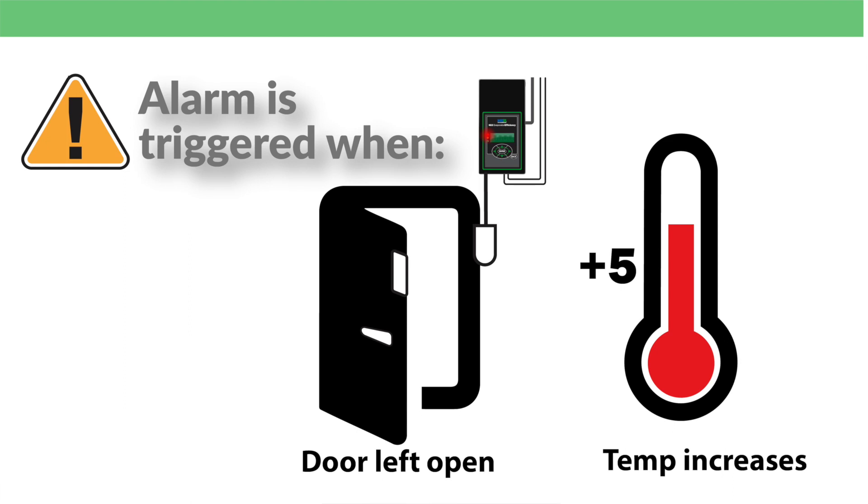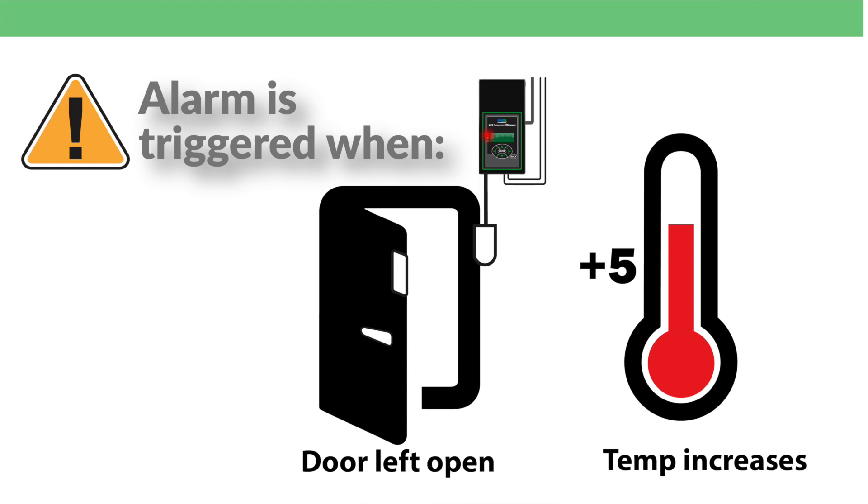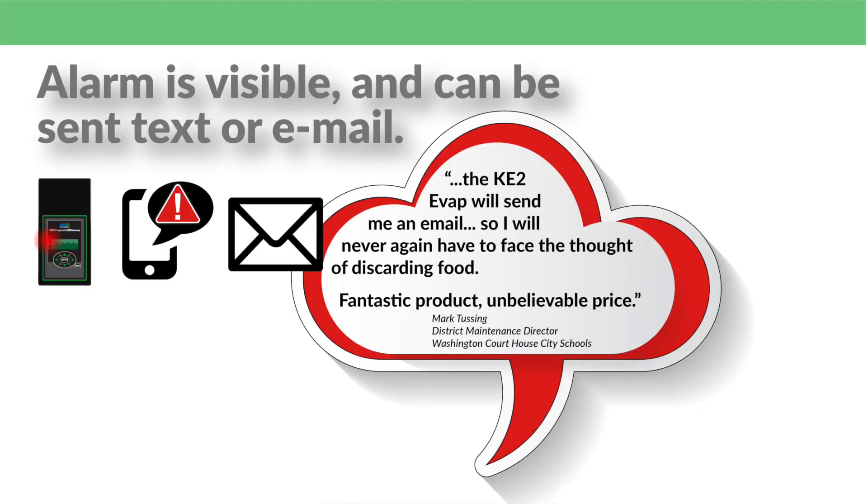But what if the door doesn't get closed all the way when you are finished loading the walk-in? Two things happen. If the temperature in the walk-in rises 5 degrees, an alarm is triggered. The alarm can even be sent to you via text or email.